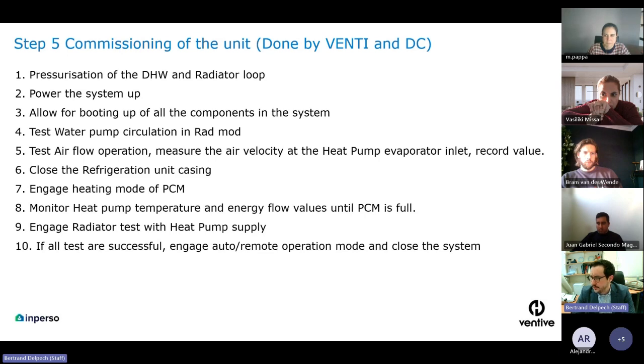We'll close the refrigeration unit and then we'll engage what's called the PCM mode. So we'll start filling up the PCM with heat, so the system is ready to be used afterward. We'll take the PCM to 57 or 58 degrees temperature, and then we're going to record those data. We're going to check that the data are in line with what we're expecting.